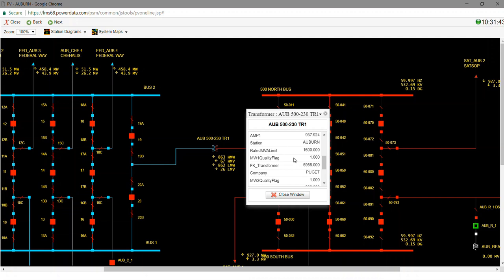Transformers can be a little harder to see. Probably the most useful bit of information from this table is going to be what the exact value of the rated MVA limit is. Transformers in particular can be kind of hard to see because there are no visual indicators. Unlike transmission lines, which have the pie charts or the line flow arrows, you can very easily see how close they are to being overloaded. Transformers are a little trickier. So if you just use the right click and device info, this will tell you exactly how far you are from your rated limit. I can see that this transformer is just over halfway loaded. So that's good information to know.